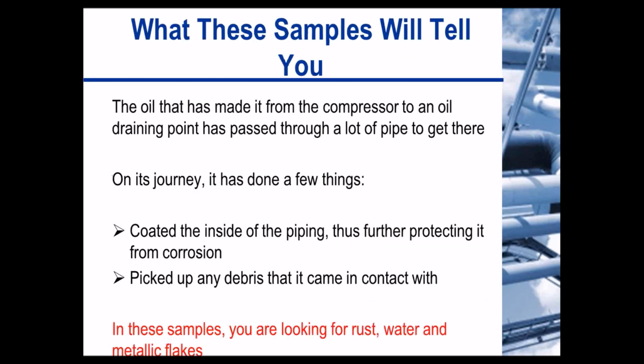So what exactly will these samples tell us? The oil that has made it from the compressor to an oil draining point has passed through the entire system. On its journey, it's probably done a few things. It's coated the inside of the piping, thus further protecting it from corrosion, and it's also picked up any debris that it may have come in contact with. In these samples, we can find a lot of information about how our system's working. We can look for rust, water, and metal flakes, and that tells us what types of issues we may encounter.